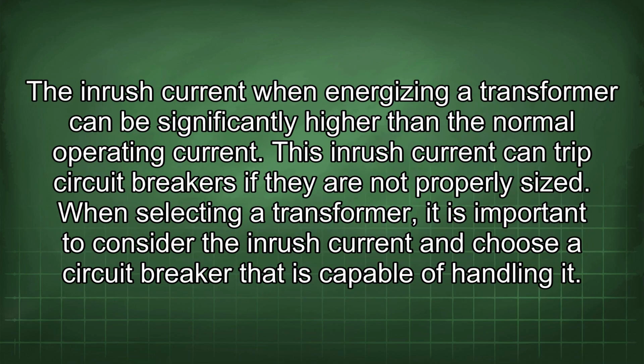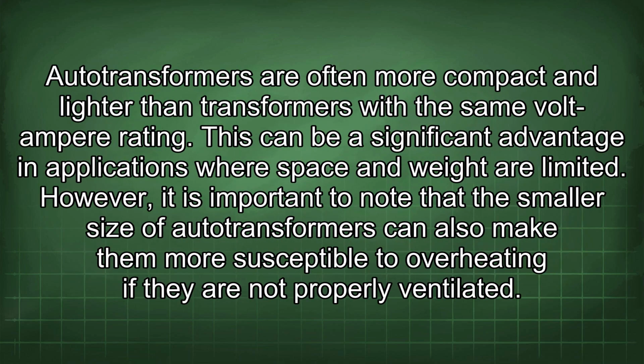The inrush current, when energizing a transformer, can be significantly higher than the normal operating current. This inrush current can trip circuit breakers if they are not properly sized. When selecting a transformer, it is important to consider the inrush current and choose a circuit breaker that is capable of handling it. Autotransformers are often more compact and lighter than transformers with the same volt-ampere rating. This can be a significant advantage in applications where space and weight are limited.